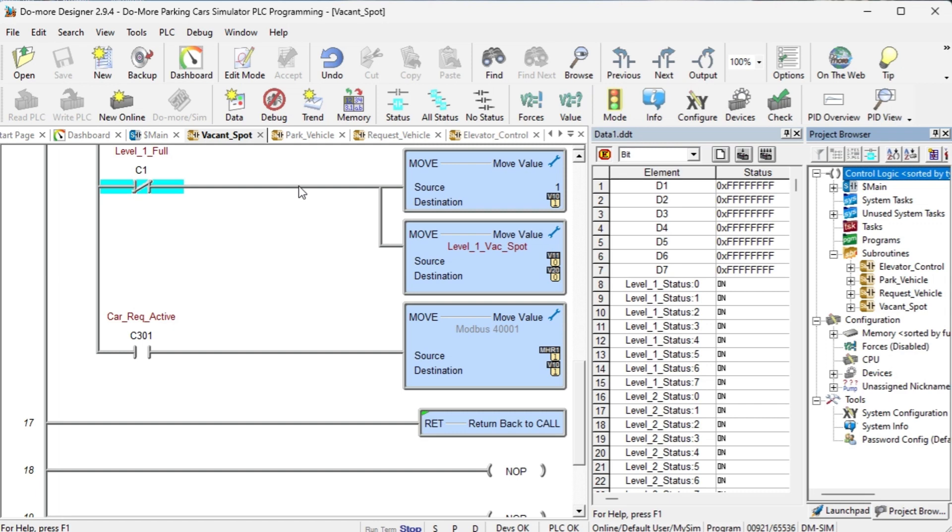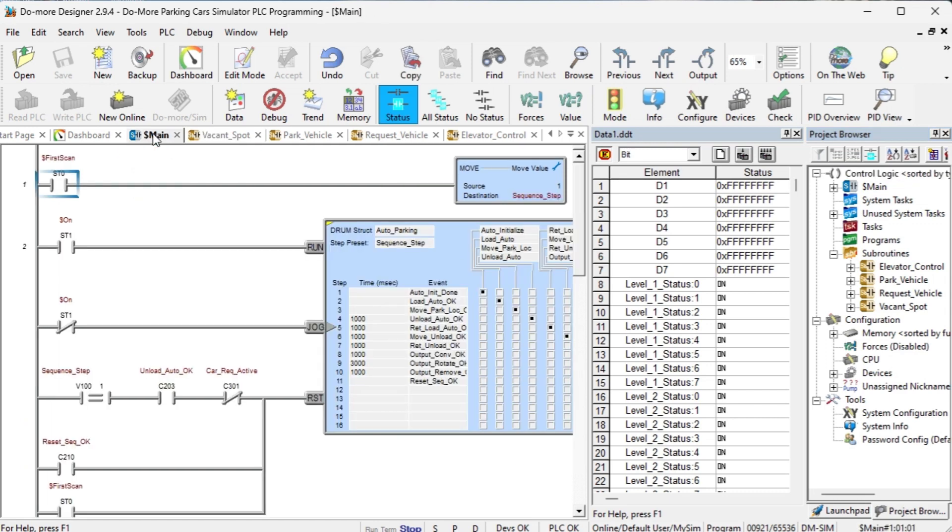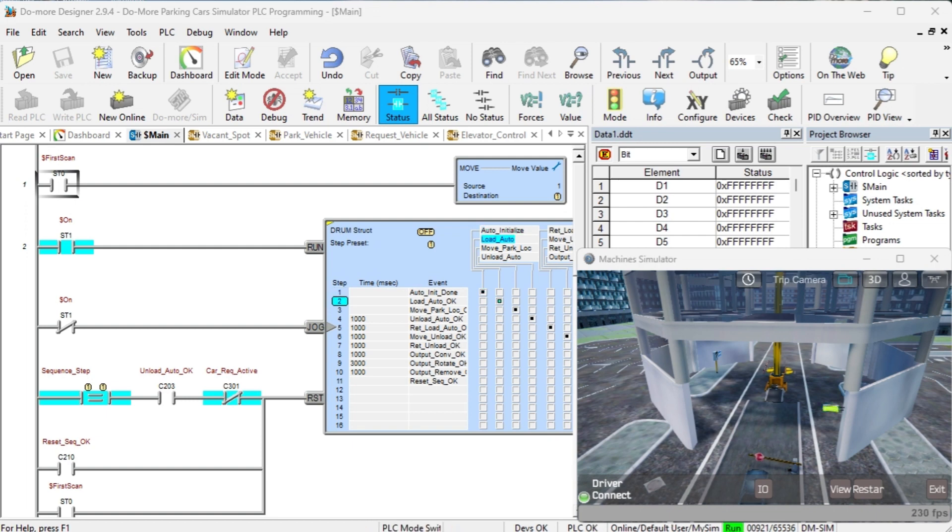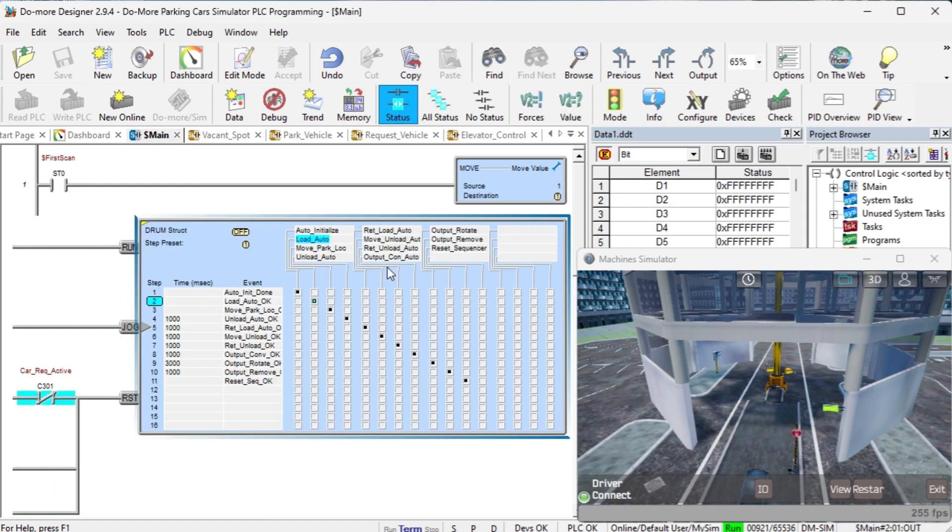Main Logic. A drum instruction is used as the main sequencer logic for the program. The first scan bit ensures that the drum will reset to step 0. The drum will reset if a car is not requested or to be unloaded at step 3. If a vehicle is to be unloaded, the drum will continue to step 11 and reset.